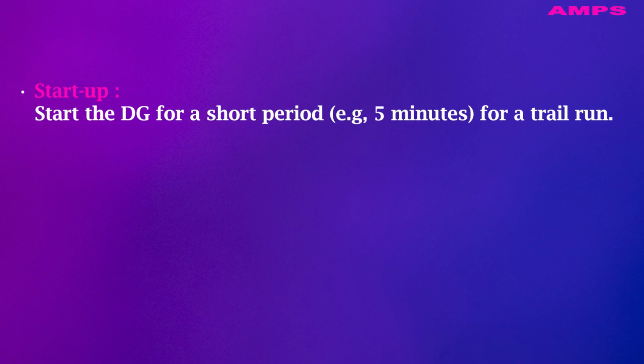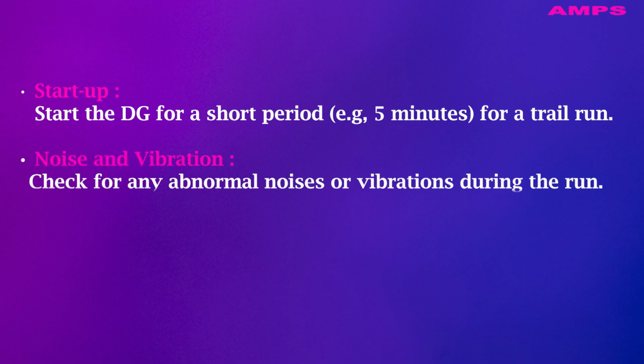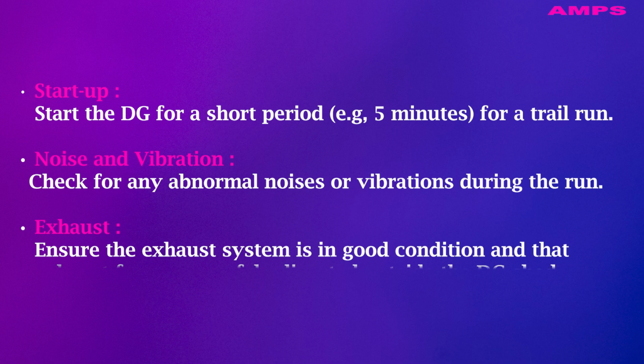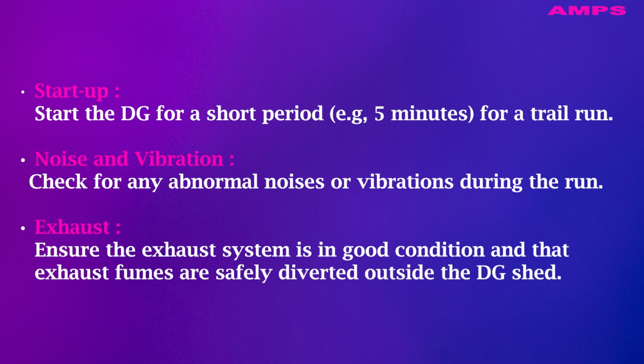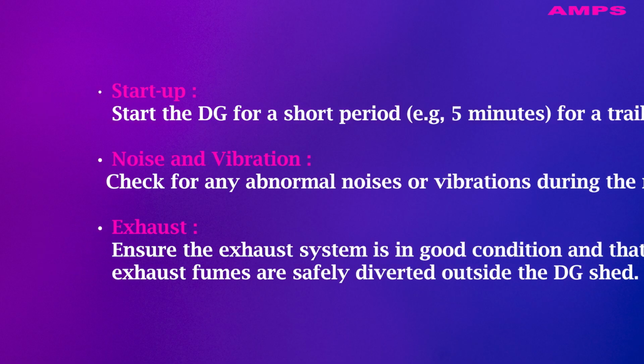4. Running and sound checks, called a test run in offload. Start up: start the DG for a short period, for example 5 minutes, for a trial run. Noise and vibration: check for any abnormal noises or vibrations during the run. Exhaust: ensure the exhaust system is in good condition and that exhaust fumes are safely diverted outside the DG shed.